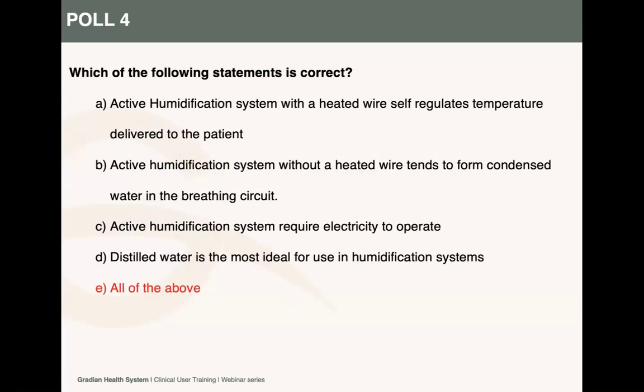And the last poll, poll number 4, the answer is all of the above. As you heard, active humidification system with heated wire self-regulates temperature. We say that active humidification system without heated wire tends to form condensed water in the breathing circuit. You will see on the water trap there will be collection of water. Sometimes the water can be seen on the breathing circuits. And the active humidification system requires electricity to operate. And distilled water is always ideal to use in humidification system. So the answer was all of the above. Next slide.